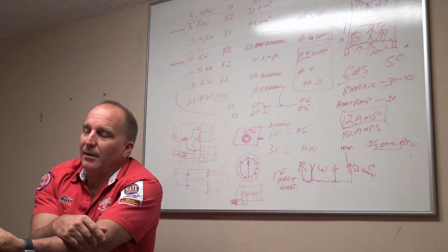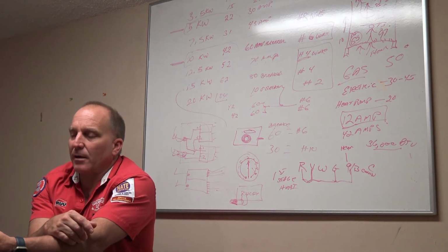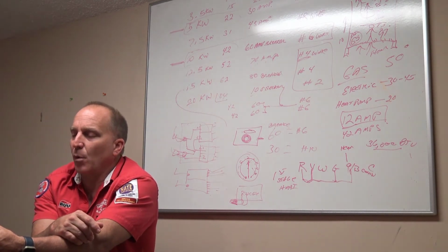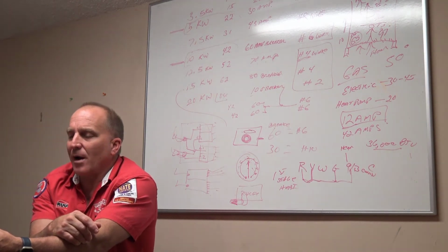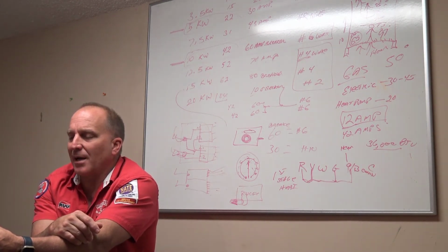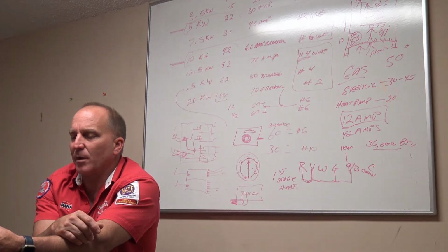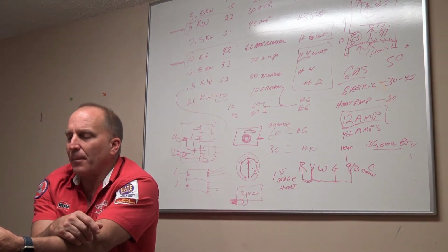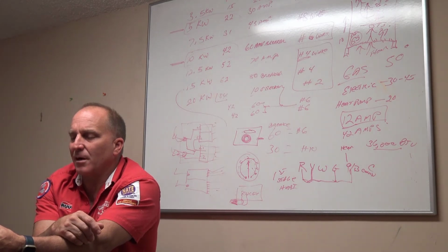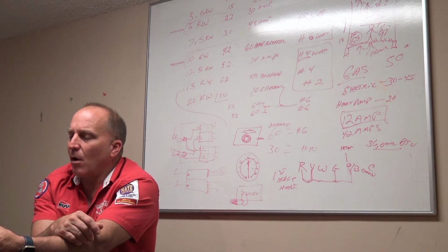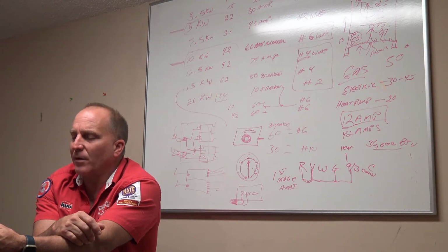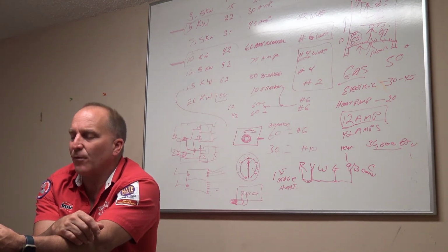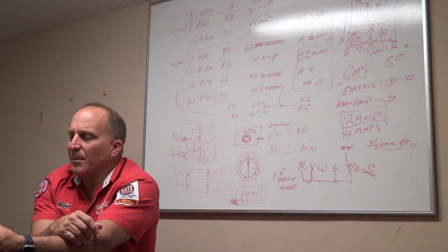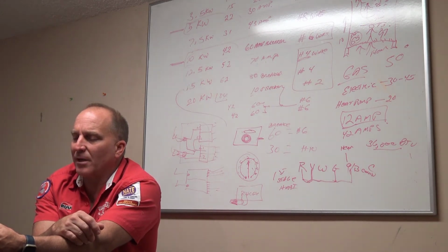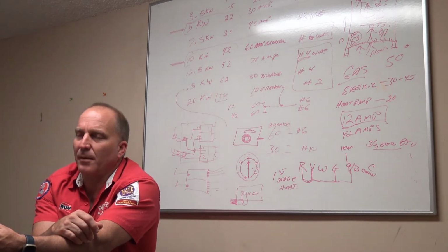All right, that concludes the electric heat system check. This is for the electric heater check portion of the PMA. Know your wire sizes, amperage, breakers, fuse sizes, delta T. All these things are extremely important to make sure you are not burning wires and the customer is safe. The customer is depending on you to check all the wire sizes and make sure all the electrical in the heating system is safe for their family. Your job is to check all the safety features for the electric heating system. Do not shortcut these steps. These could cause fire and possible death.